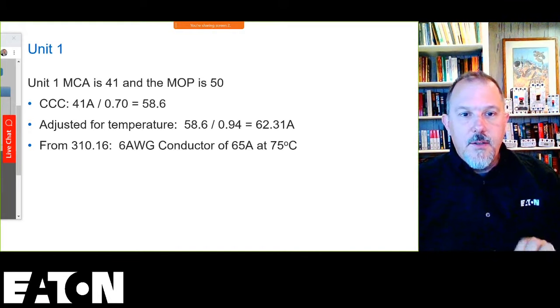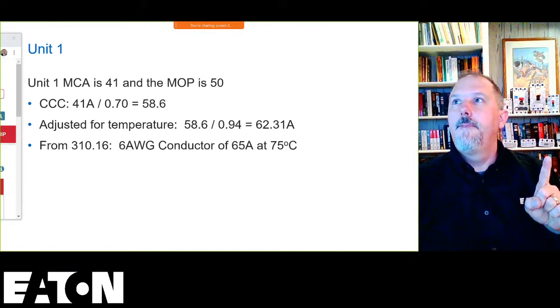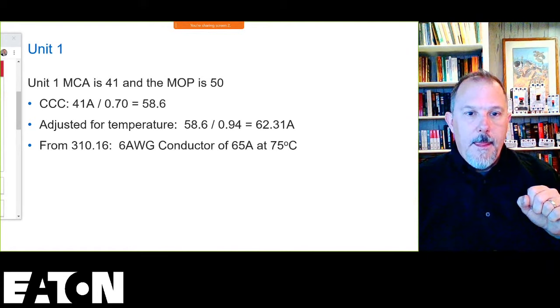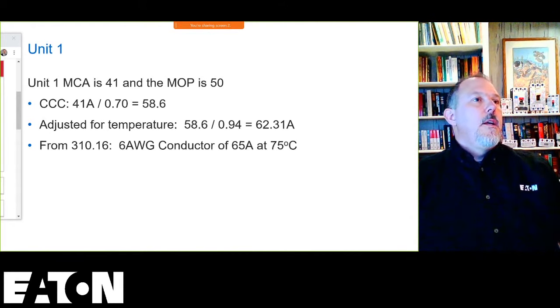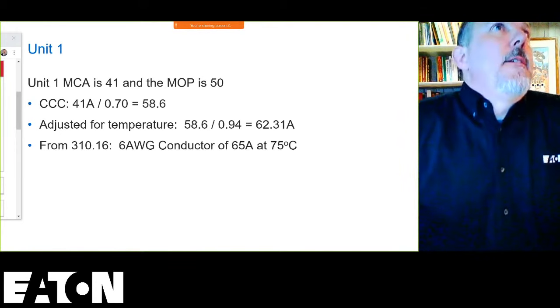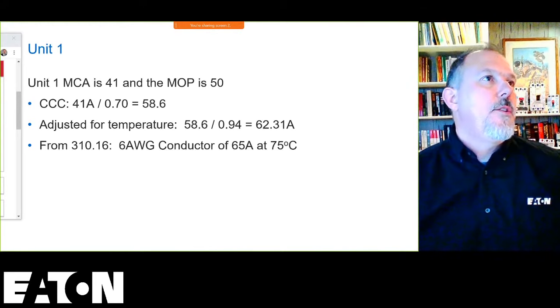As that's opening, my first answer is a number 6 for the current carrying conductor. Let's take a look at the YouTube responses. THWN-2, I see all that. I'm going to scroll all the way to the top. David Engelhart, you had a number 6 on unit 1, so you got the same number as I did. I'm not sure what you used for ambient temperature, but you have that.